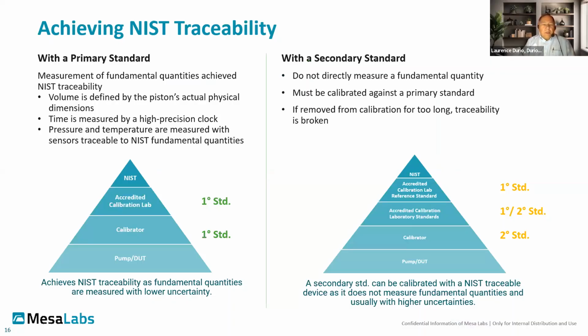These are just quick and dirty. These are the pyramids of traceability and unbroken string of traceability for a primary standard. A secondary standard, you've got breaks for analogies and for having to calibrate a secondary standard with a primary standard. We're not going to put a lot of time into this. When you get the slides, you can take a look at it yourself. But basically, the secondary measurement has at least one level and sometimes multiple levels of analogy. I won't go so far as to call it guesswork, but assumptions at least.